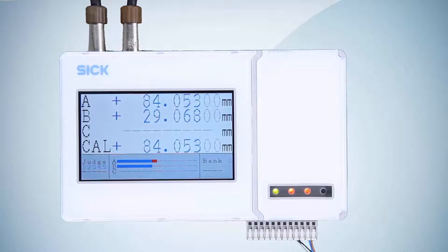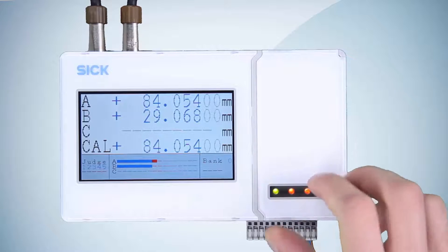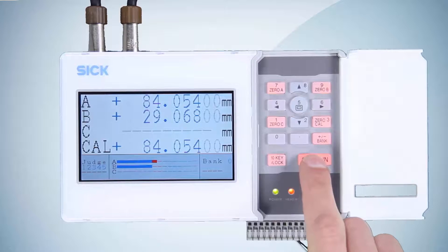Now we come to making the settings for thickness measurement on the device. Please check that the device is set to the factory settings and carry out a reset if necessary. To access the menu, press the Set Run pushbutton once.